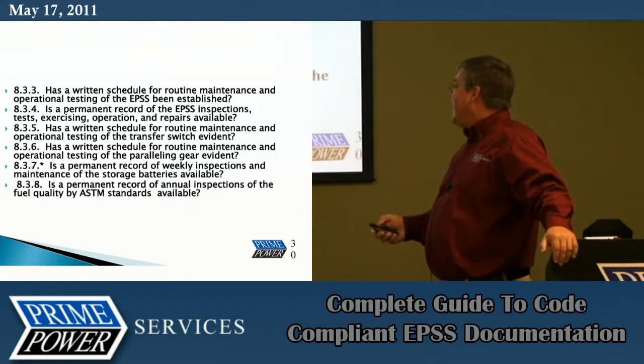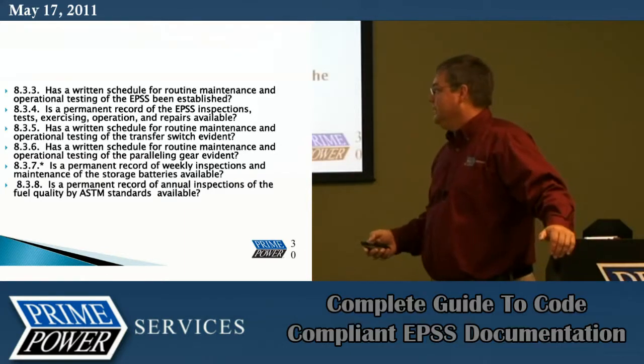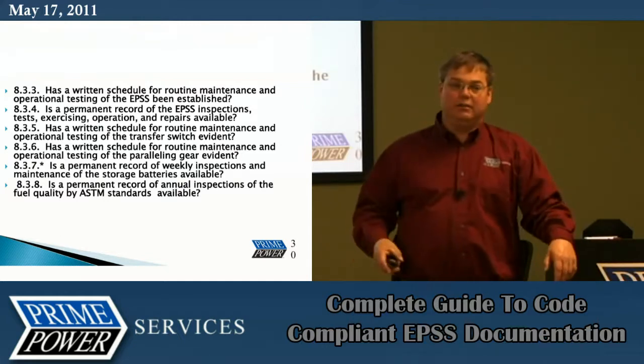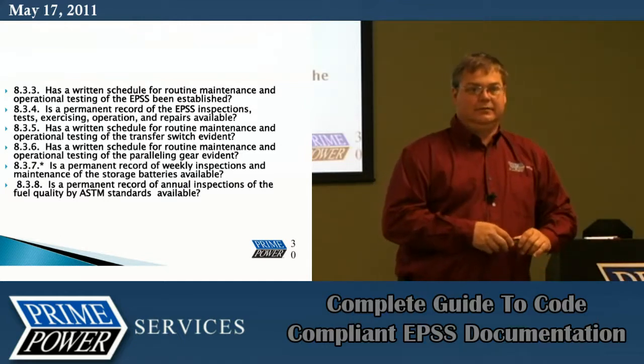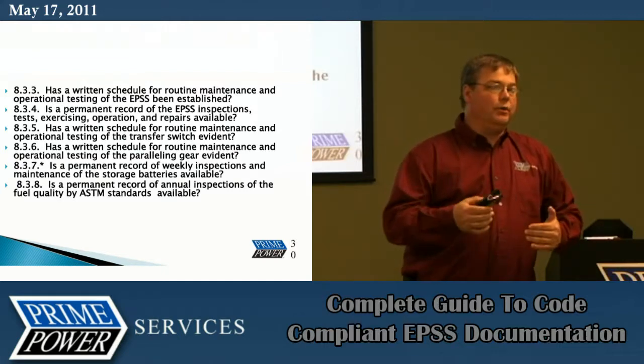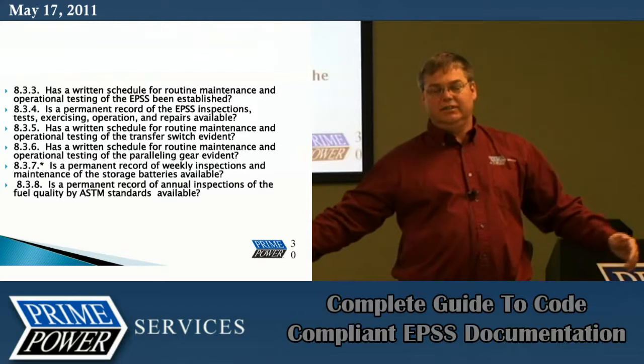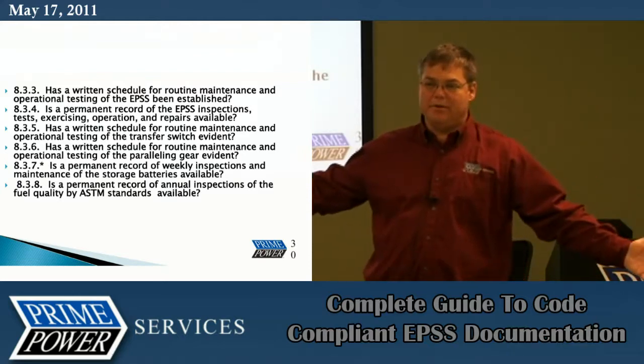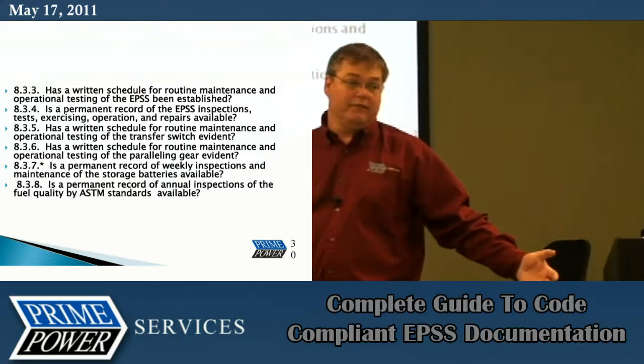Is a permanent record of annual inspections of the fuel quality by ASTM standards available? You're required to do an annual fuel analysis. All right? Now, the idea on the fuel, we'll go ahead and talk about for a moment. You've sometimes got these humongous tanks out there that you'll never burn up in 3 or 4 years. Very important to do that fuel testing.